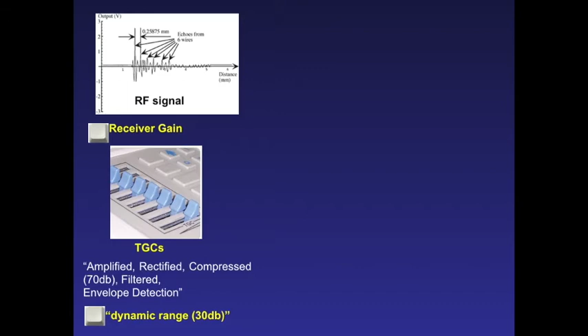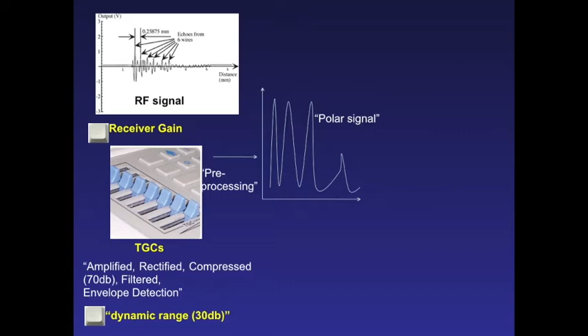So through TGCs, we change our RF signal so that you don't have the natural loss in voltage due to attenuation. We amplify this RF signal, we rectify it, compress it, and filter and envelope detect it. And once you do, and fit it into a dynamic range of about 30 decibels, you end up with a polar signal, which is all positive, which you've assigned now through post-processing 30 to 50 shades of gray.